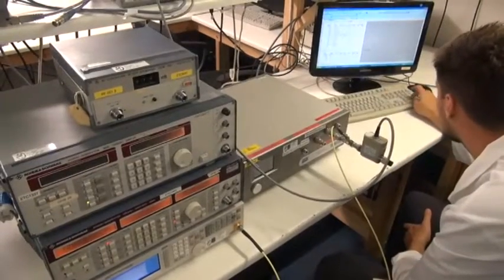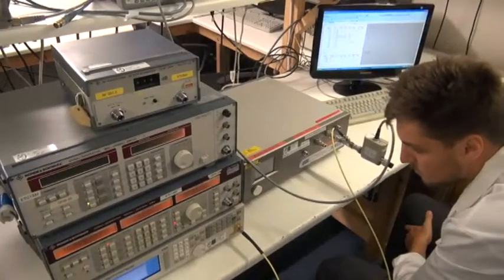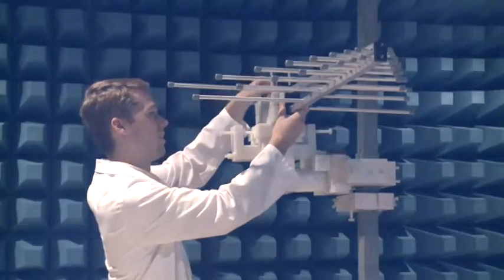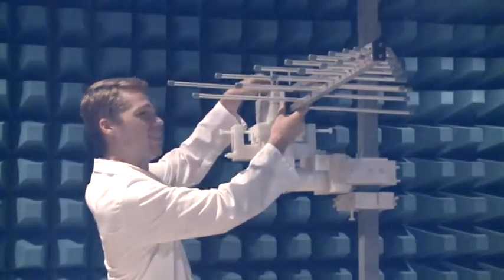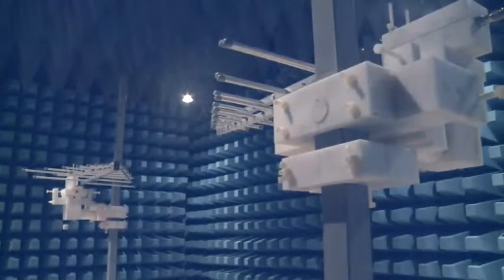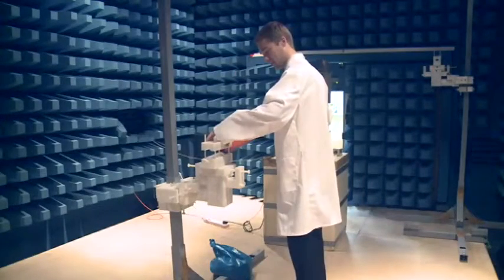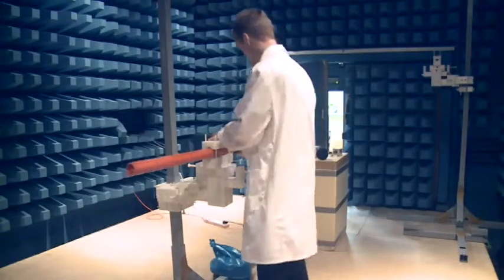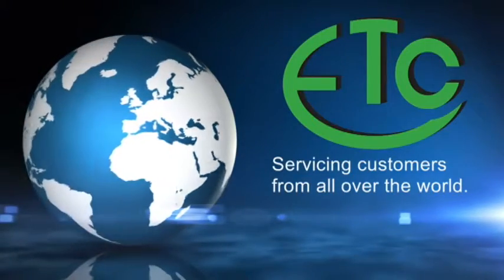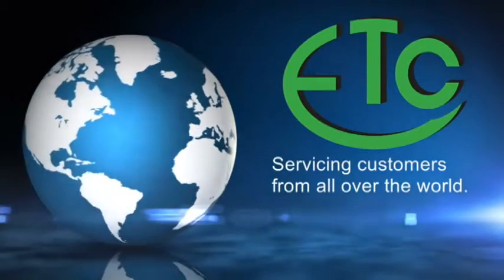We can currently offer traceable calibrations from 100 kHz up to 40 GHz. We calibrate coupling networks, amplifiers and other RF hardware and antennas for EMC testing labs throughout the UK and Europe, and we currently have customers in over 30 countries around the world.